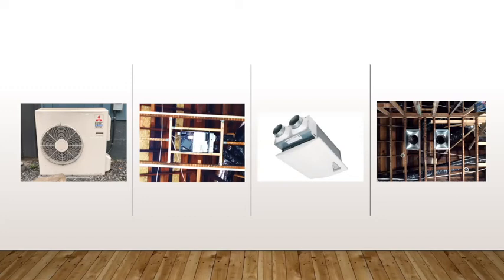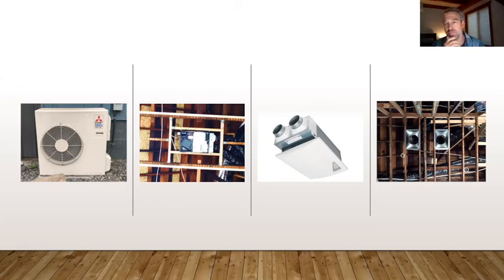Sorry, you just have one in the whole building? Yeah, and so you put them in the large public area. On a bigger house, we would have one per floor. In our office, we just have one in the main central area, and it services the whole floor. Panasonic makes a larger ERV that has 4 ports instead of 2 ports, and that one you could actually run pipe to every single room. Like if you've got a top floor with a lot of bedrooms and all the doors are closing off the airflow, then you would use a different ERV with 4 ports, and you would actually run pipes to each room.